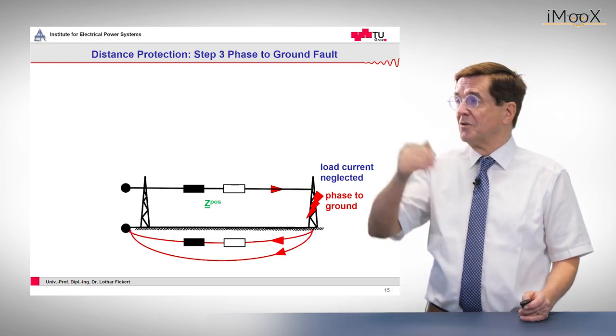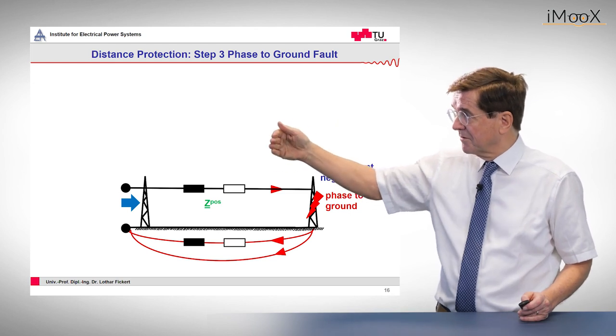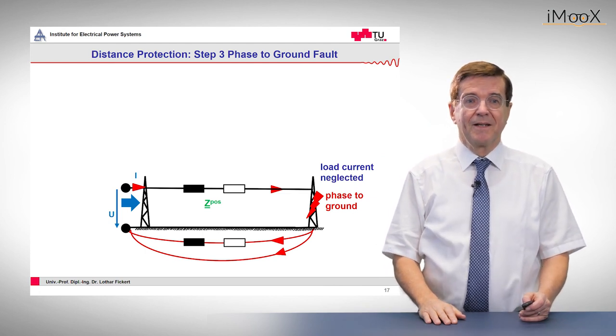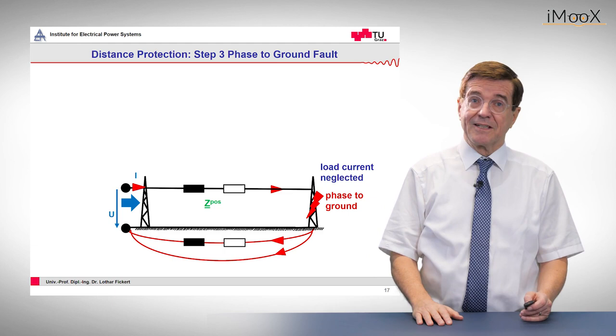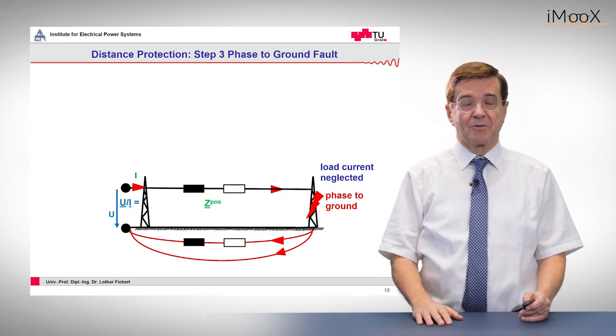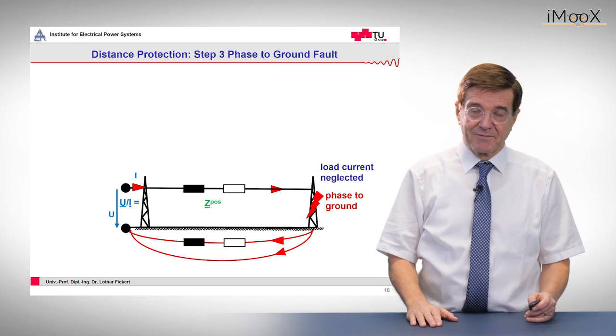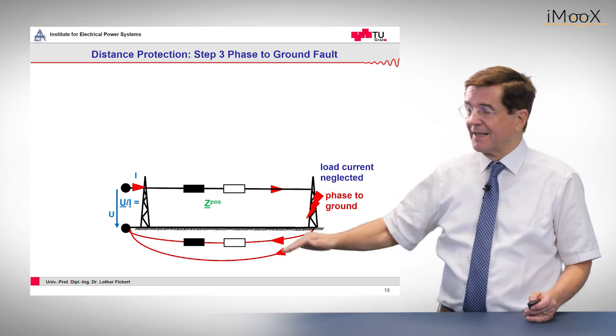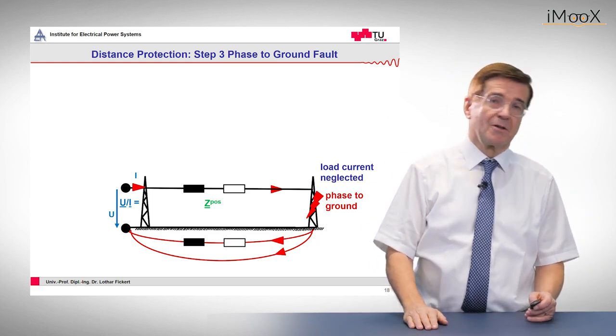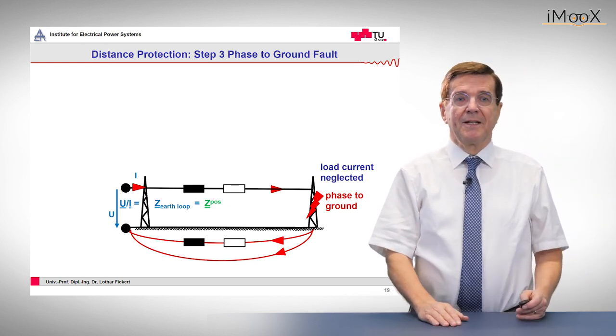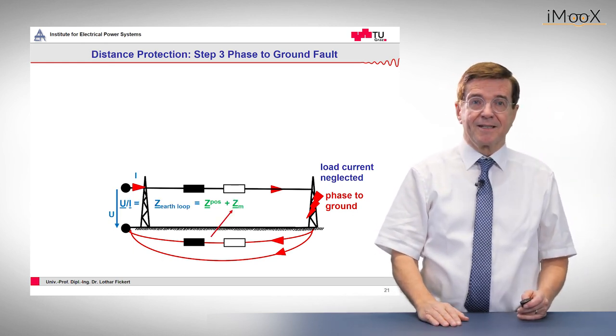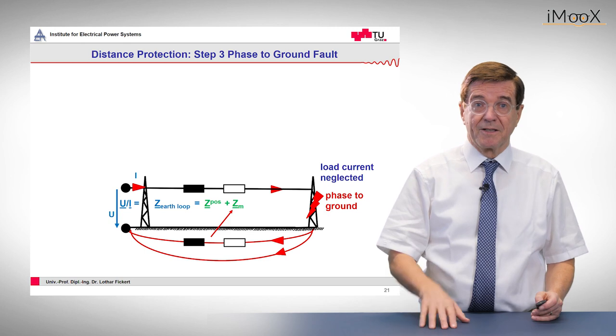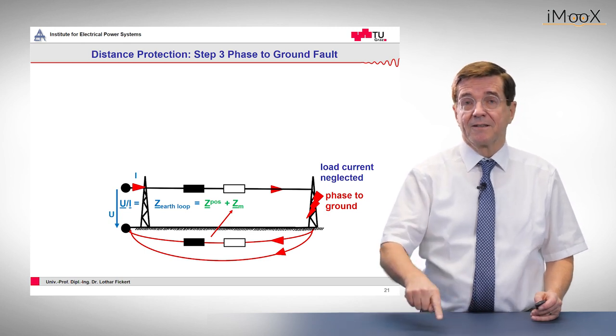The current comes from the left through the line, goes down to ground, and returns through the ground path. The distance relay measures the phase-to-ground voltage and the current, and from this it would like to conclude what is the impedance value of the fault. The whole loop is made up of the positive sequence impedance — some people say the impedance above ground — plus the earth impedance, which is underground. By the way, in a cable network it is the sheath impedance.